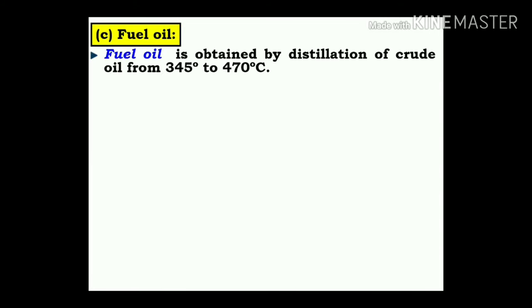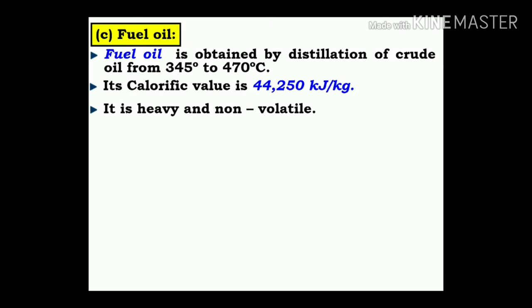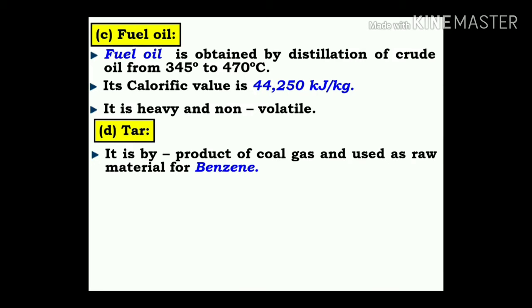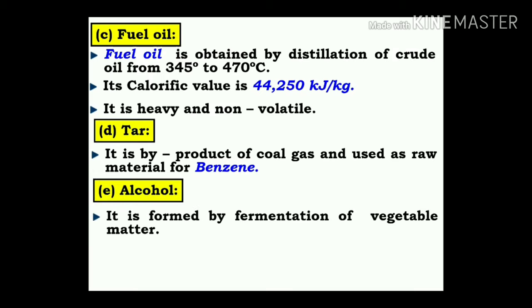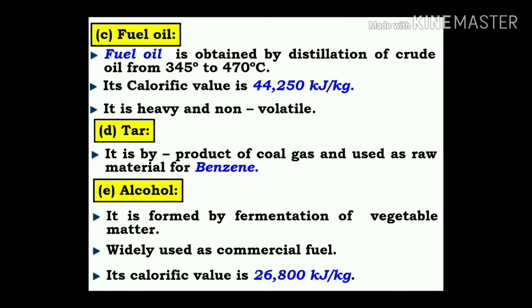Fuel oil is obtained by distillation of crude oil from 345°C to 470°C. Its calorific value is 44,250 kJ/kg. It is heavy and non-volatile. Tar is a by-product of coal gas and is used as a raw material for benzene. Alcohol is formed by fermentation of vegetable matter and is widely used as a commercial fuel. Its calorific value is around 26,800 kJ/kg.